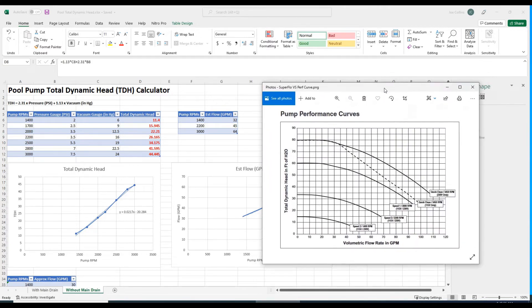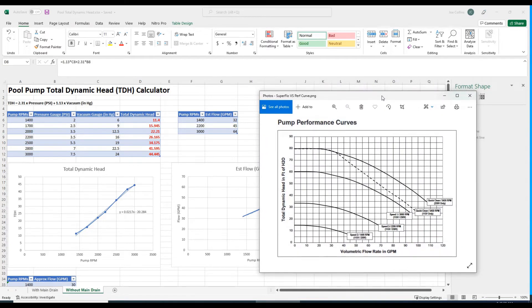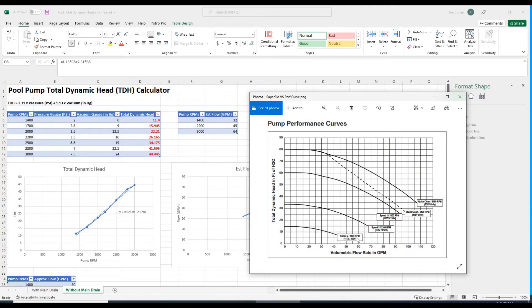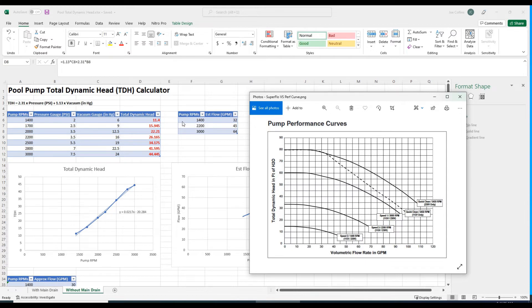Now we take this total dynamic head figure coupled with the pump RPMs and look up the flow rate using the pump's performance curve. I have a SuperFlo VS pool pump by Pentair. This is the performance curve that Pentair publishes for this pump. We see curves at 1400 RPMs, 2200 RPMs, and 3000 RPMs.